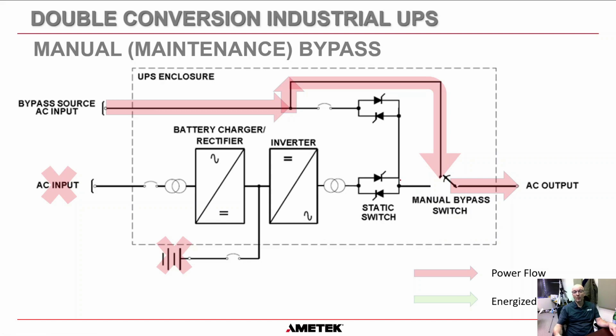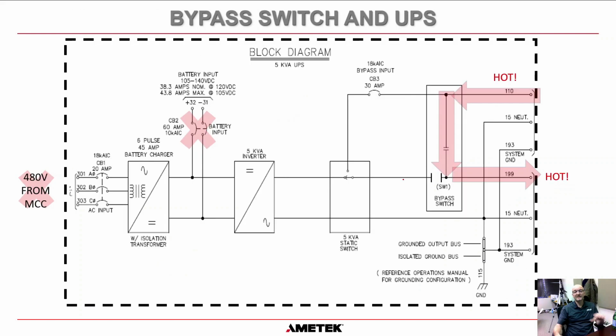But there is a problem with this design. And here's a better drawing where you can see all the input terminals to one of our UPSs. Here's the bypass switch that we just mentioned, and this is in the bypass position. Actually, I made one minor mistake. That is actually closed. So when we have it in this position, the power flow is coming from your bypass, from your MCC, and it flows into the UPS through the bypass switch and back out to your load circuits. Okay? Internal to the UPS.